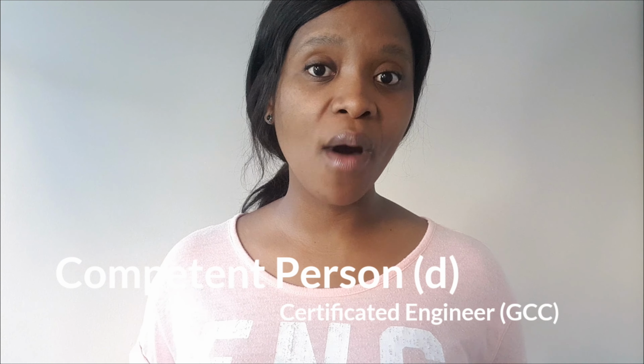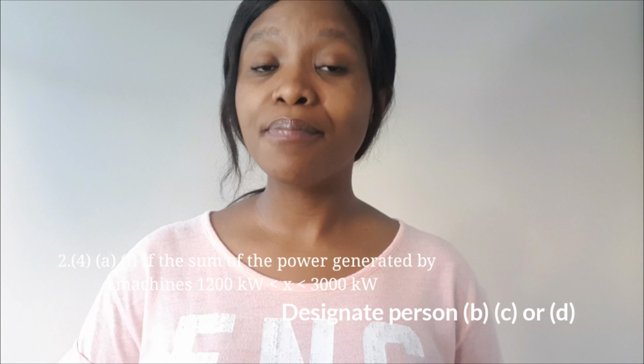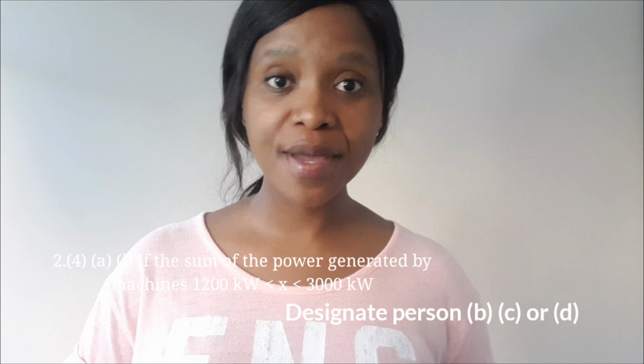It goes further to detail who must be appointed or supervise your site and machinery under what conditions. So if you've got power generation, even power derived from sources like steam, greater than 1,200 kilowatts but less than 3,000, your competent person must be B, C, or D. Remember, B is with a diploma, C is a graduate engineer, and D is a certificated engineer.